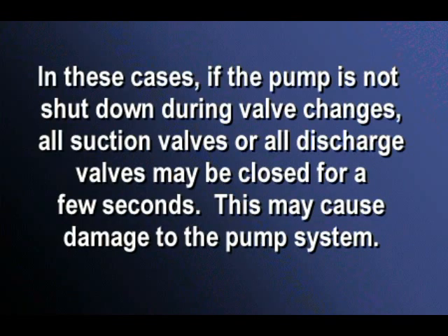down. Frequently, pumps can operate from 2 sources or deliver to separate tanks at different times. In these cases, if the pump is not shut down during valve changes, there is a danger that during the changeover, all suction valves or all discharge valves may be closed for a few seconds and cause damage in the pump system.